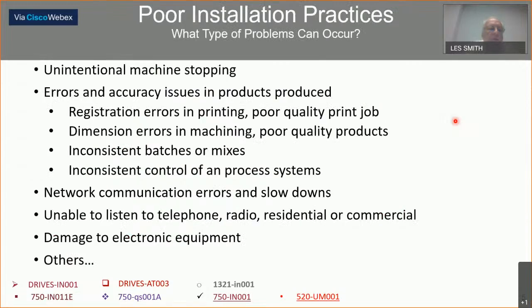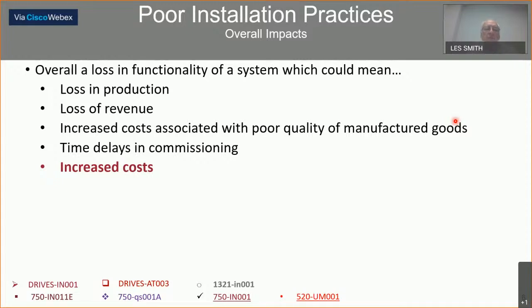The problems are obvious. Unintentional machine stopping. We have errors or accuracy issues that can show up in registrations and dimensioning, feeders, etc. Batches aren't correct, and the control process is not running smoothly. Network communications problems can appear, and you're unable to listen to the telephone. If I have a drive down in a manhole next to a stoplight, we should put a filter on it so when you're sitting there, you don't hear the drive ramping up, pumping the sludge water out of the town. Damage to electric equipment. We'll touch on this many times more down the road here. Overall impacts: loss of production, loss of revenue, increased cost, time delays in commissioning, increased cost, and that hurts everybody.